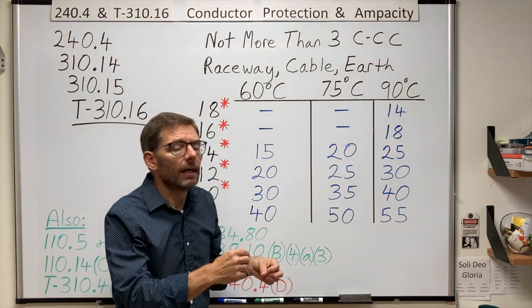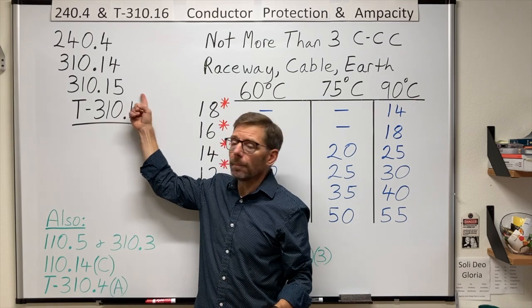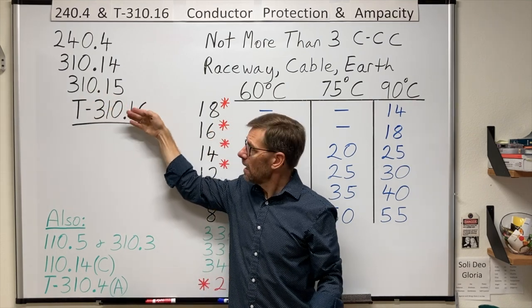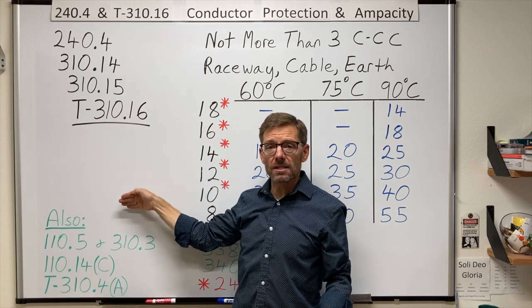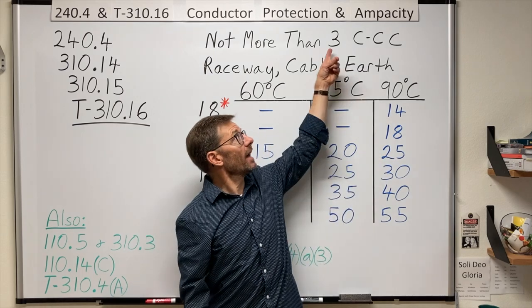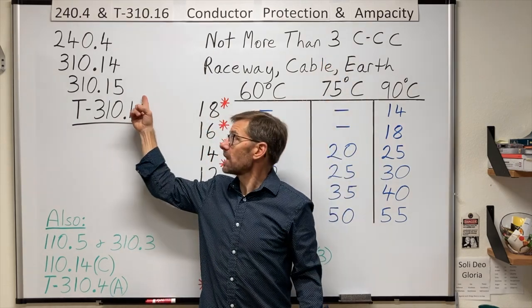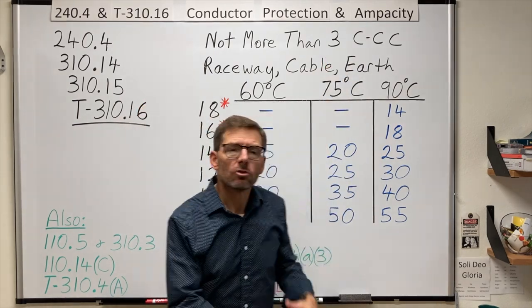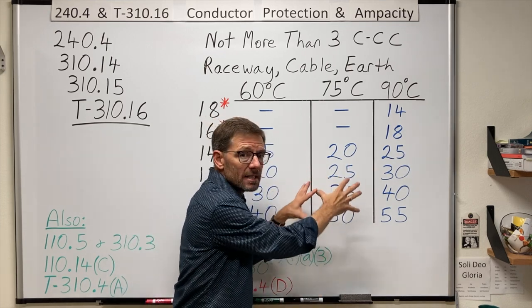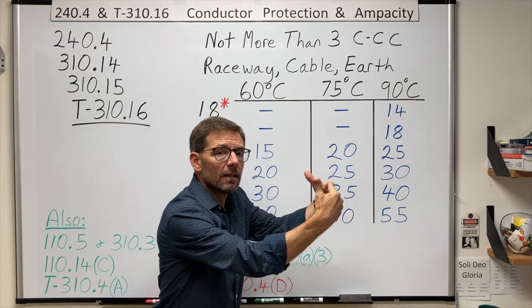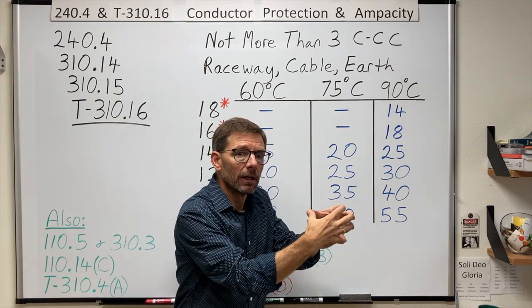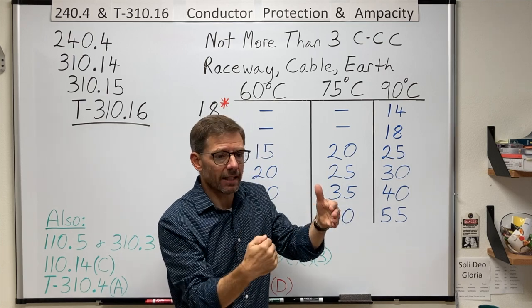Well, yes. Remember that modified thing back here? In 310.15c, it says use the ampacities from the tables, but it answers the question if I have more than three of them. Subsection C. Too much for this video, but what it basically tells me is I would use one of these ampacities and then de-rate it. I would have to take that number and reduce it slightly.